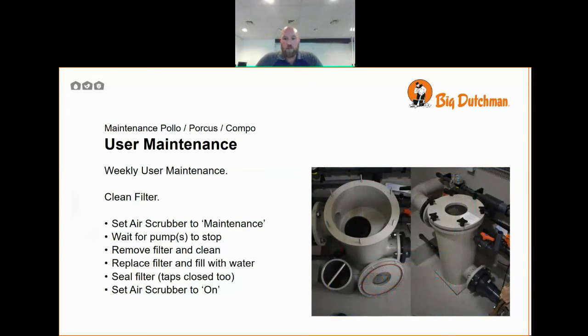Remove and clean the filter basket that's inside the filter housing. Replace the filter filled with clean water. Seal the filter, replacing the lid and sealing down with the 6 hand buttons, relatively tight. You do not need a tool to close these handles. Hand tight is sufficient. On larger systems, make sure they're tightened up as hand tight will go. Ensure that both taps are closed too, and then set the air scrubber back to on.